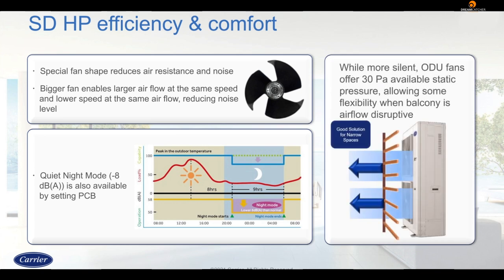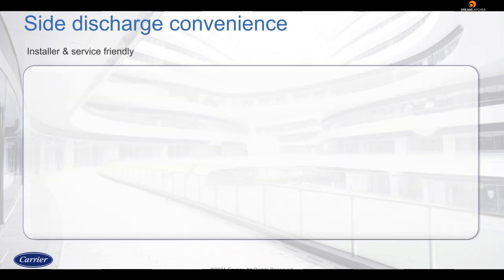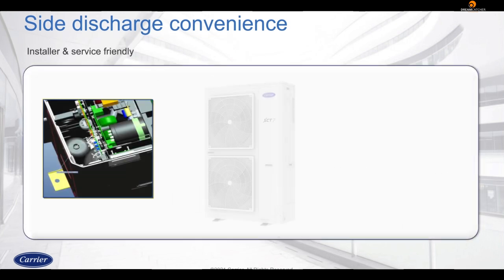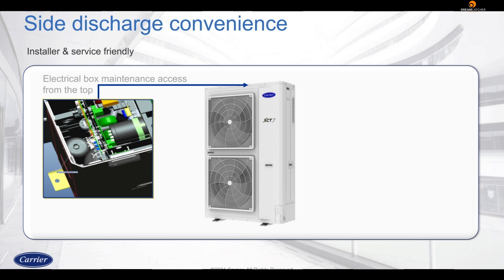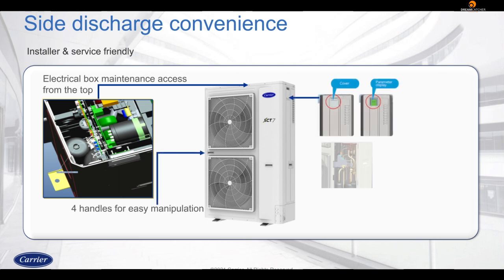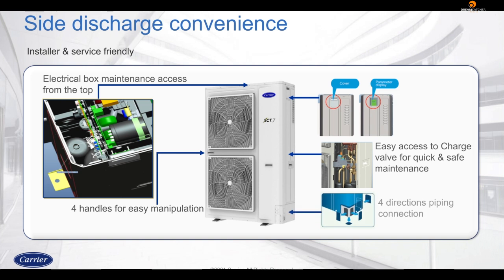And it does so without compromising on performance through the ODU fan that offers 30 Pa static pressure, even when installed in areas that are airflow disruptive. The side discharge setup offers easy installation with a 4-direction piping connection, easy access to charge valve for quick and safe maintenance, 4 handles for ease of manipulation, and top access to the electrical box maintenance.